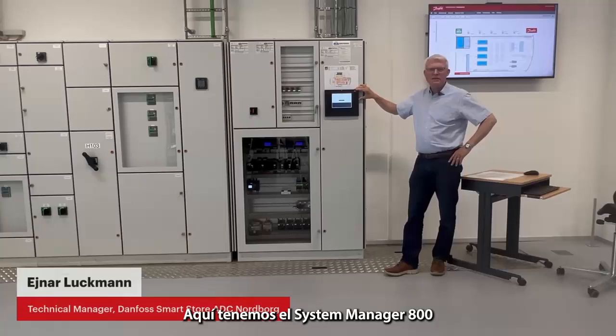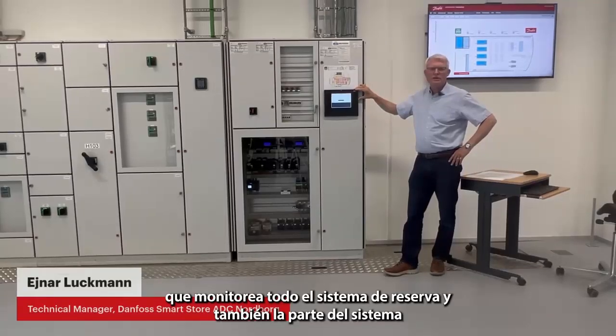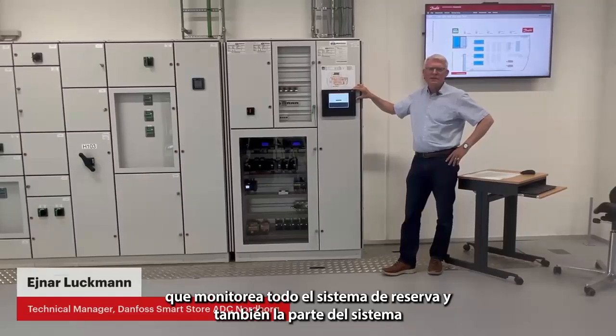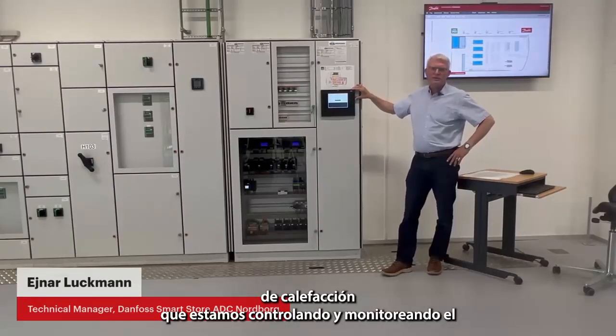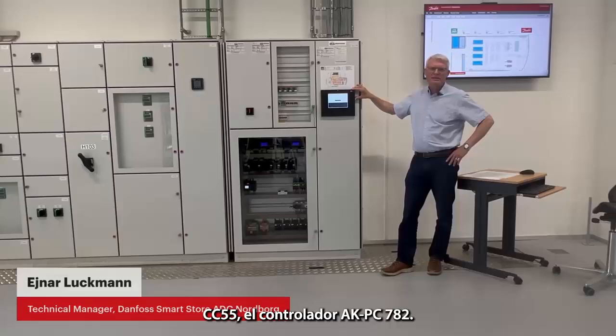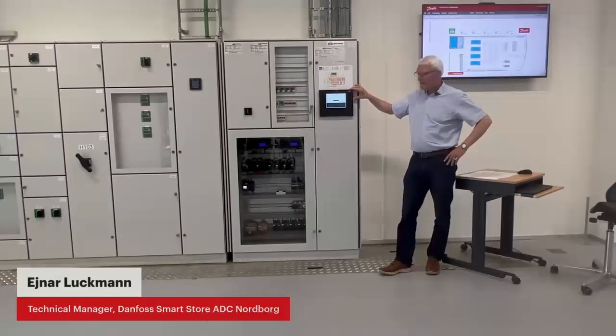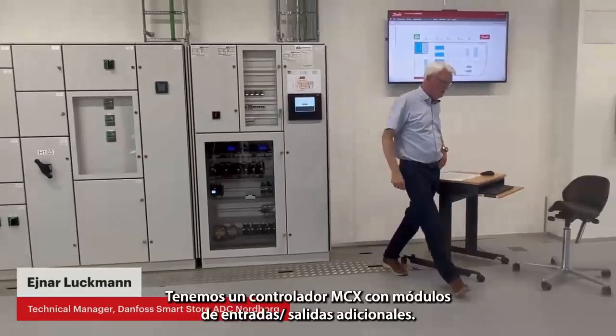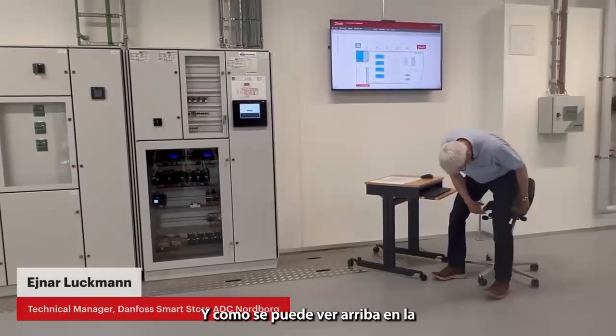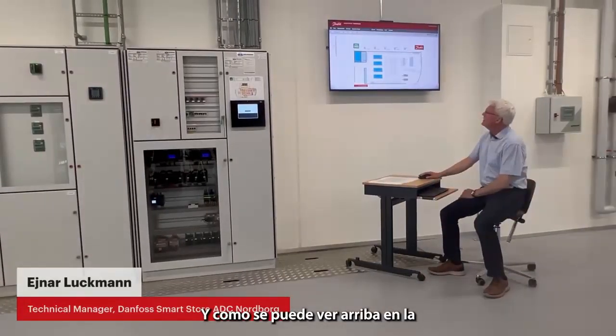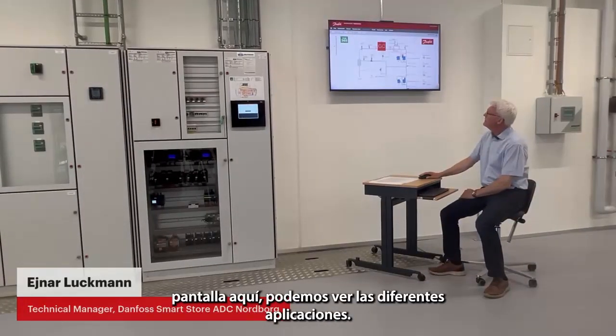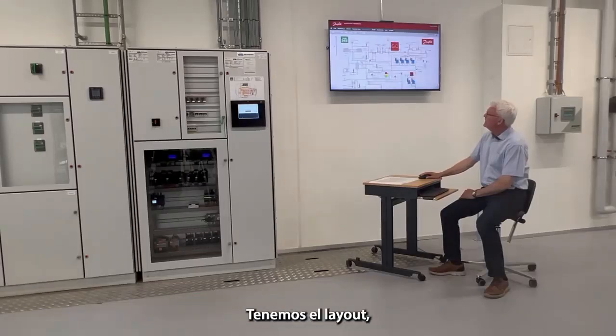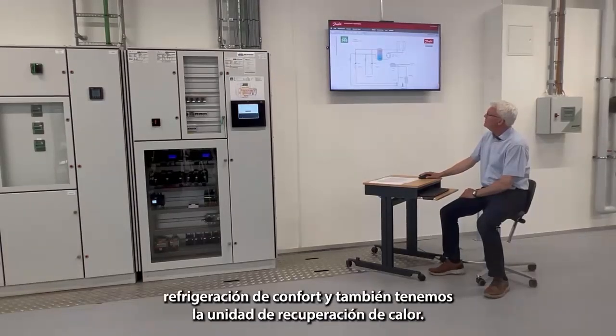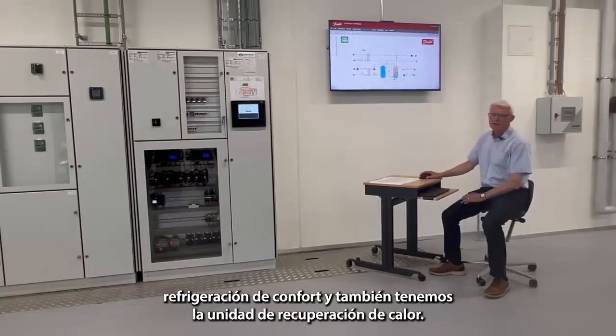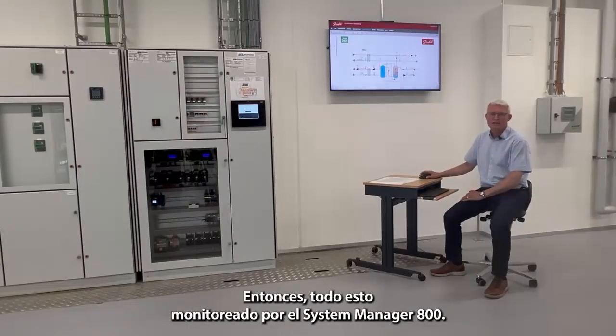Here we have the System Manager 800, which is monitoring the whole refrigeration system and also part of the heating system. We are controlling and monitoring the CC55, the pack controls, the PC782. We have MCX control, we have extra IOs, and as can be seen on the screen here, we can see the different applications. We have the store layout, the standard pack, the advanced pack, the comfort cooling, and also the heat recovery unit. So all this is monitored by the System Manager 800.